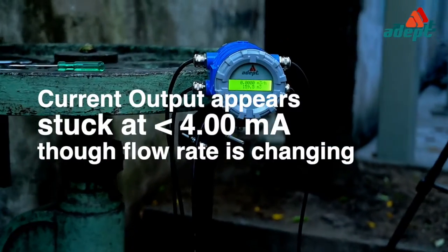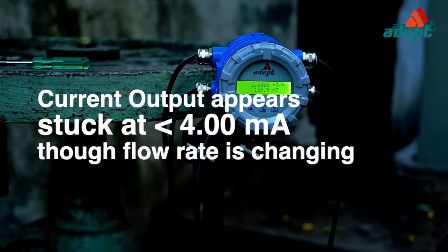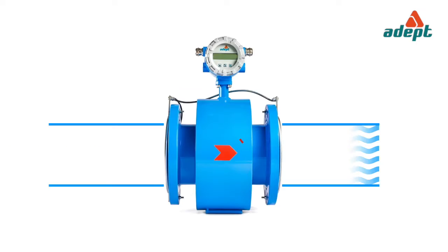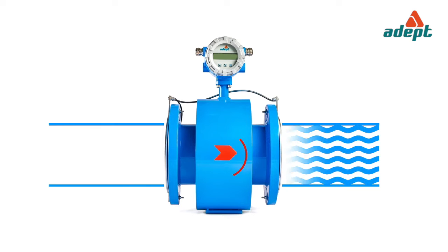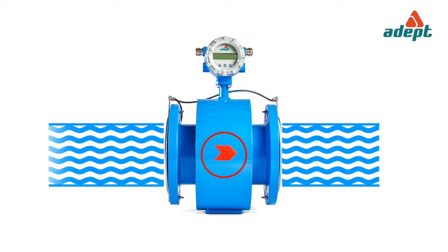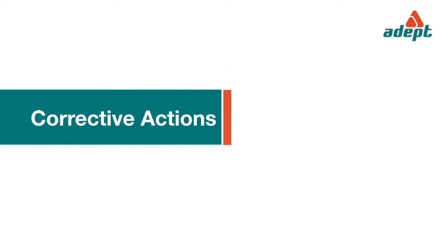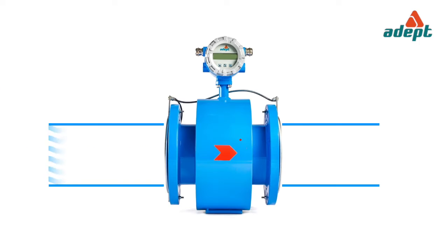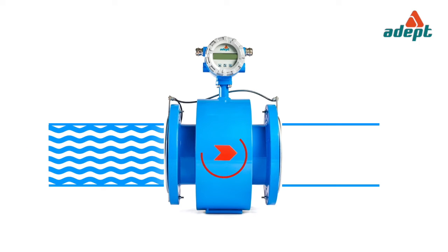Current output appears stuck at less than 4 mA though flow rate is changing. Possible cause: the direction of actual flow is opposite to the arrow mark on the flow tube. Corrective action: reverse the flow tube and check.